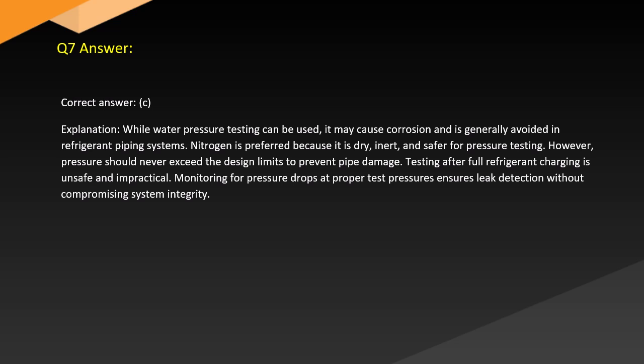Answer. Correct answer. C. Explanation. While water pressure testing can be used, it may cause corrosion and is generally avoided in refrigerant piping systems. Nitrogen is preferred because it is dry, inert, and safer for pressure testing. However, pressure should never exceed the design limits to prevent pipe damage. Testing after full refrigerant charging is unsafe and impractical. Monitoring for pressure drops at proper test pressures ensures leak detection without compromising system integrity.